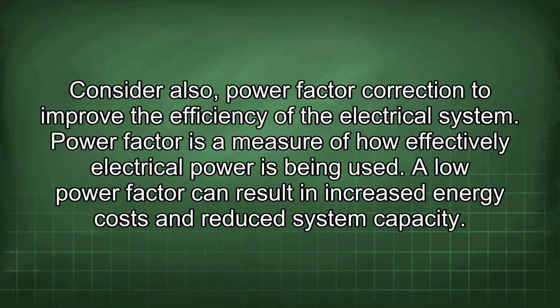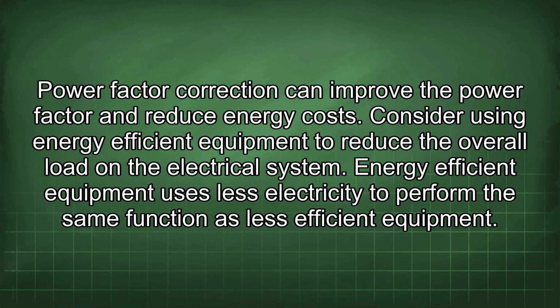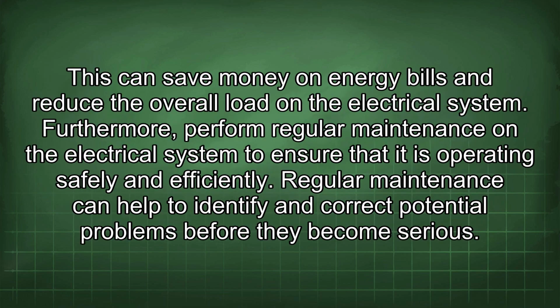Power factor is a measure of how effectively electrical power is being used. A low power factor can result in increased energy costs and reduced system capacity. Power factor correction can improve the power factor and reduce energy costs. Consider using energy-efficient equipment to reduce the overall load on the electrical system. Energy-efficient equipment uses less electricity to perform the same function as less efficient equipment. This can save money on energy bills and reduce the overall load on the electrical system.